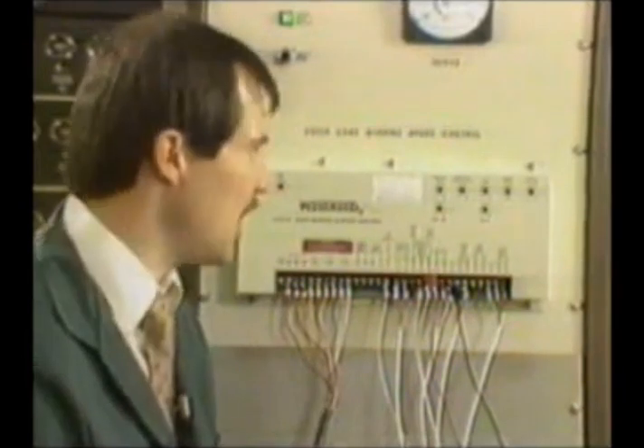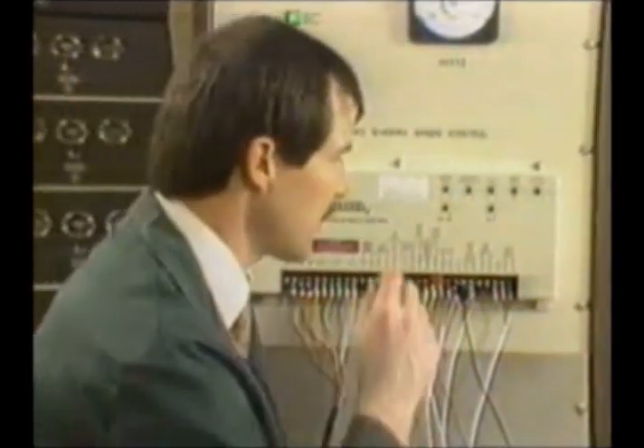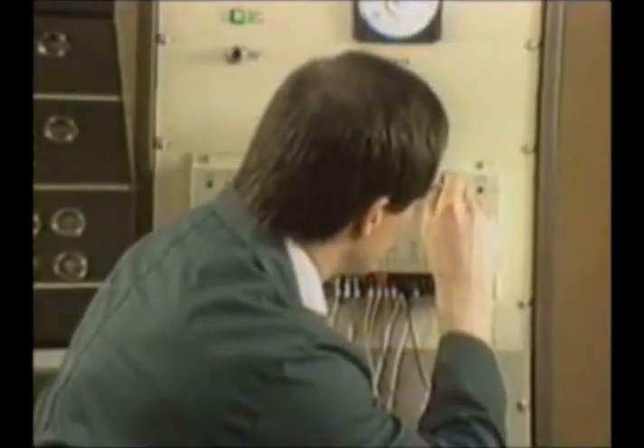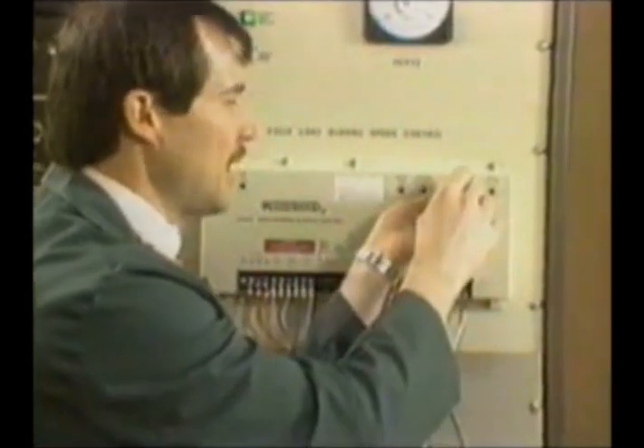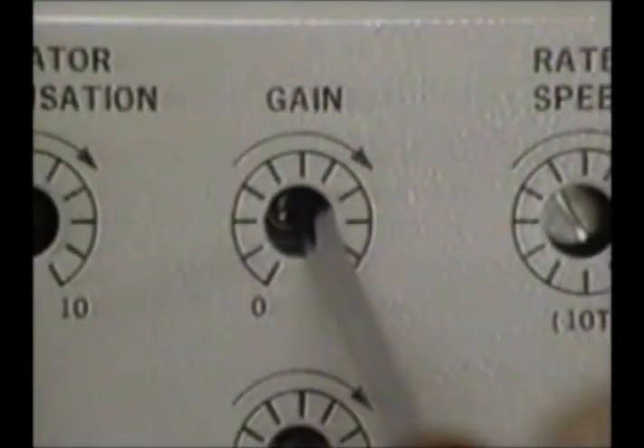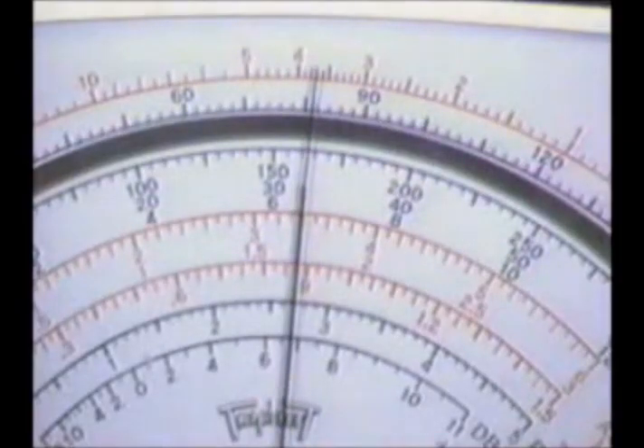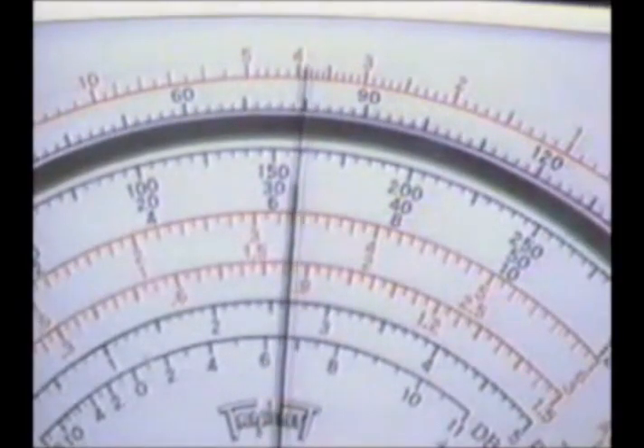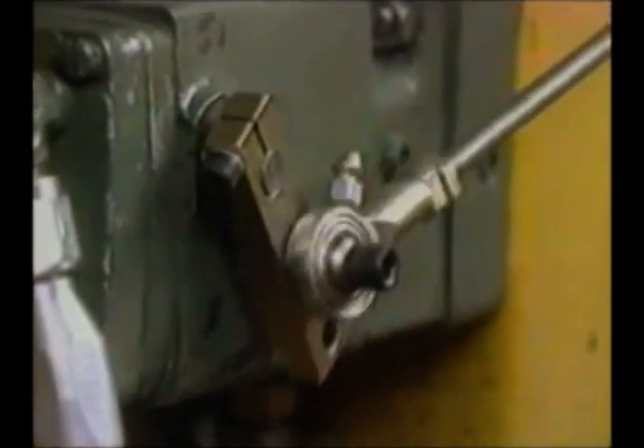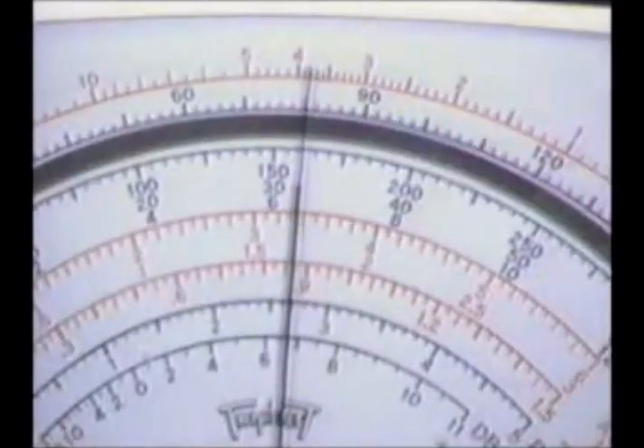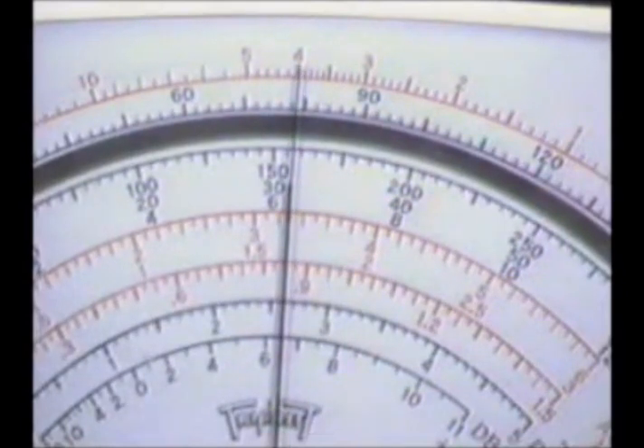Then I'm going to back my gain pot counterclockwise till I'm stable. Now turning my gain potentiometer will cause a momentary speed change. So to minimize this speed change, I'm going to turn the pot very slowly. As I turn the pot, the analog meter shows you that we are now unstable, and you can hear the actuator. Let me back off. Okay, now the analog meter shows that we're stable.